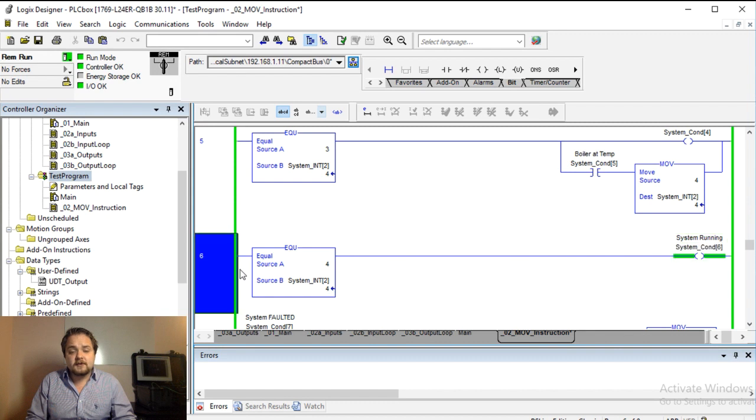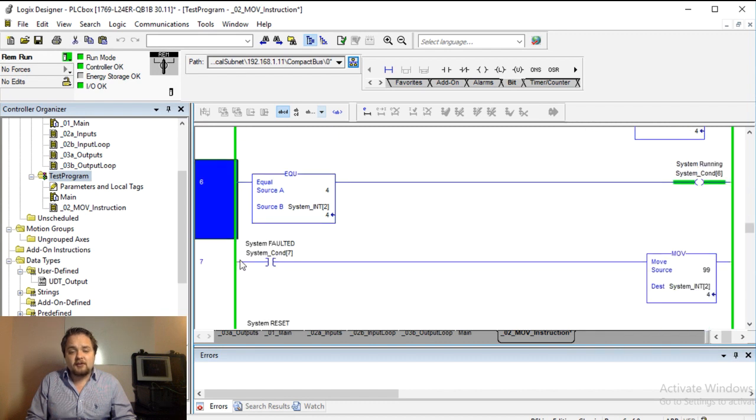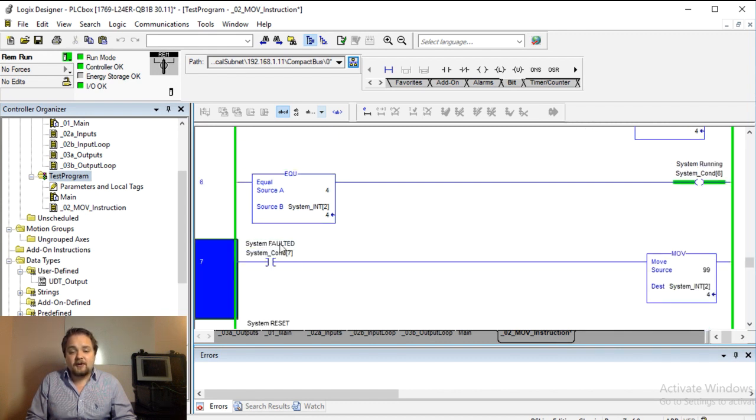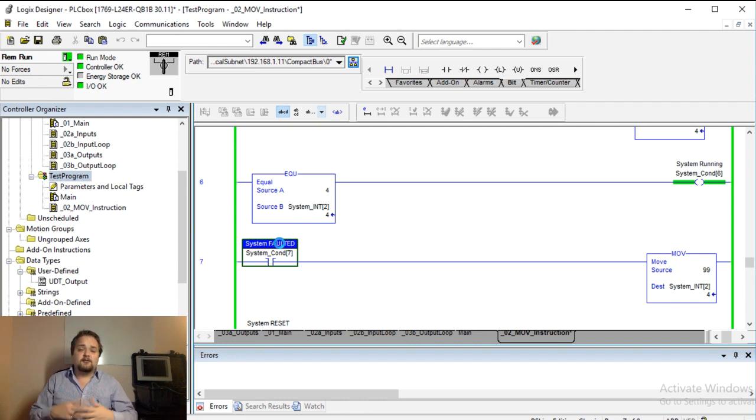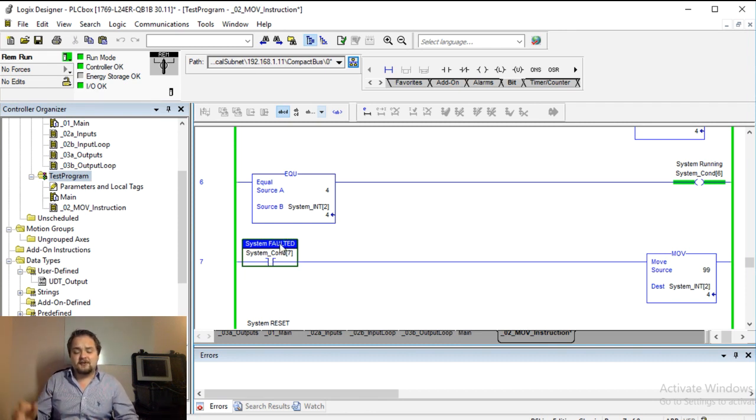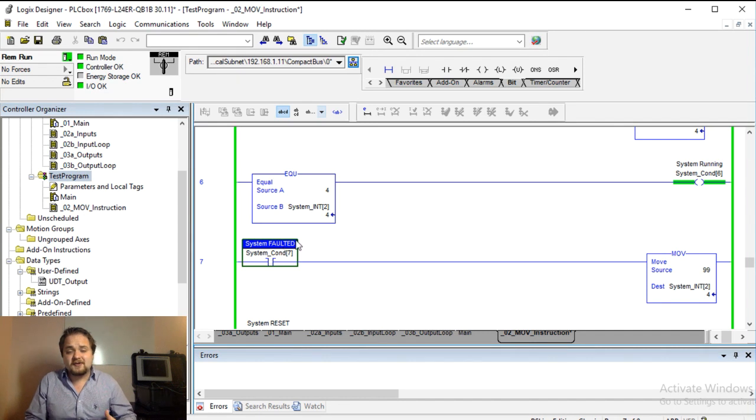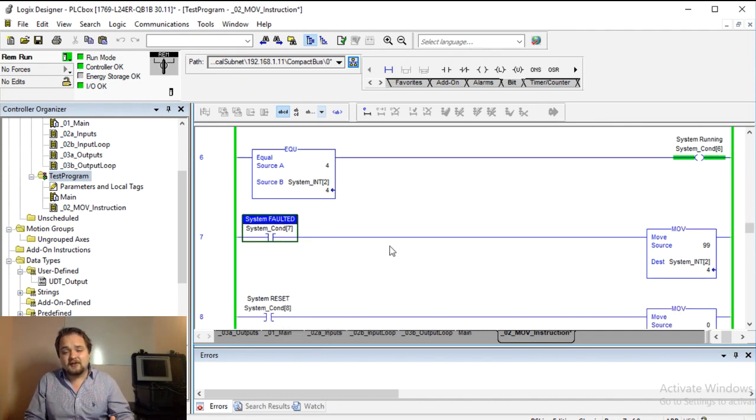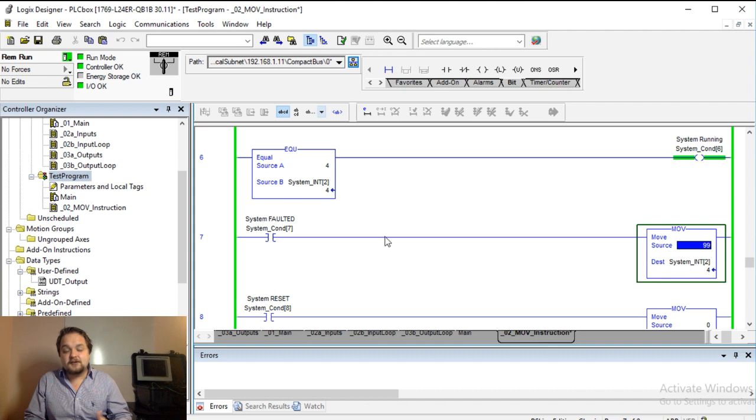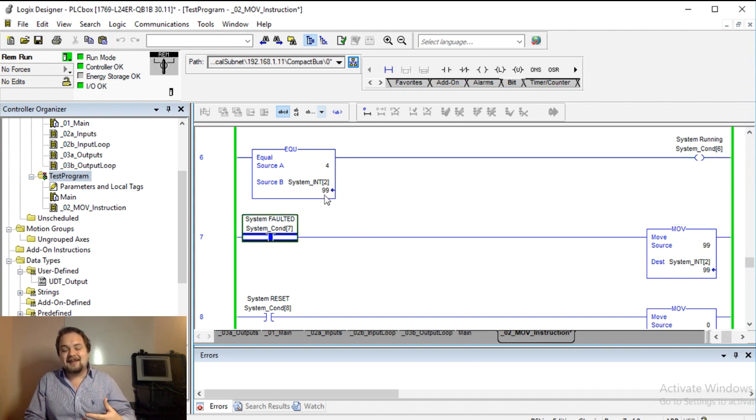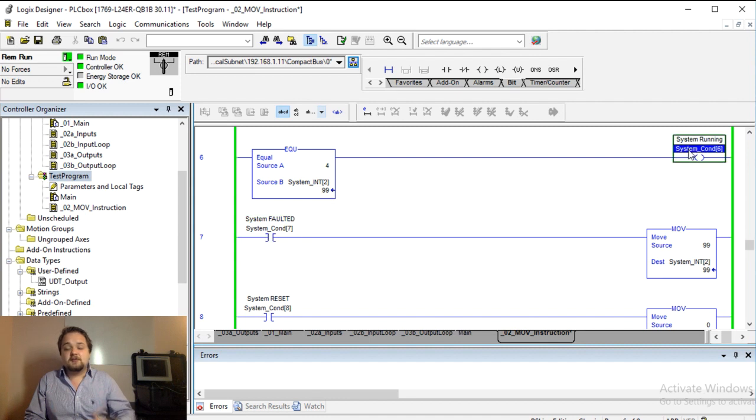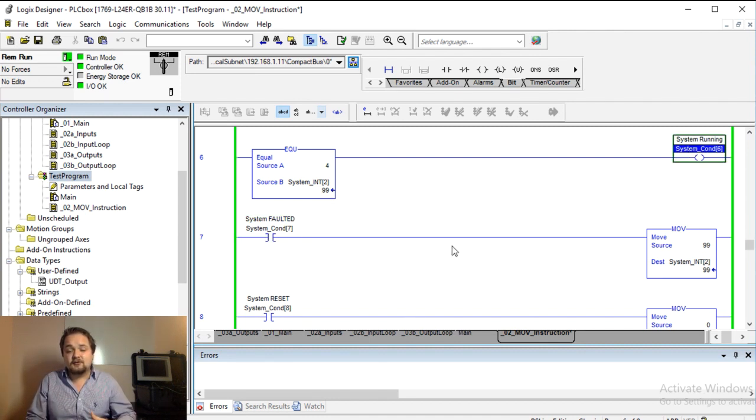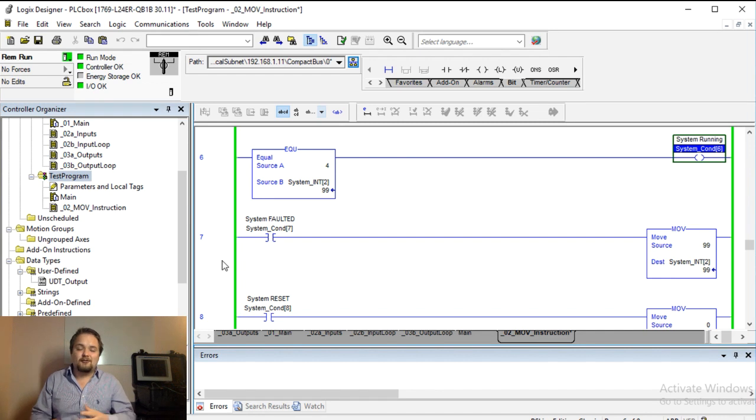For example, if you have this system faulted bit, so here if whatever fault, and of course we can detect it in many different ways. I made a video right before this about different alarms and how to detect them. But if the system is faulted, we're going to move this 99 into our integer. So let's look at this for a second. As soon as we move that 99 you will notice that the system is no longer running, so it's in this shutdown state.